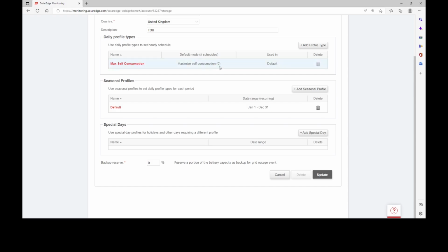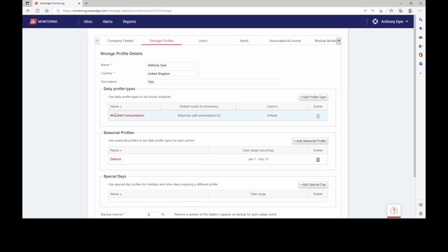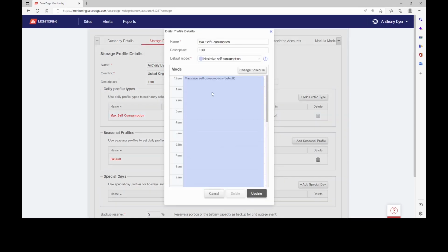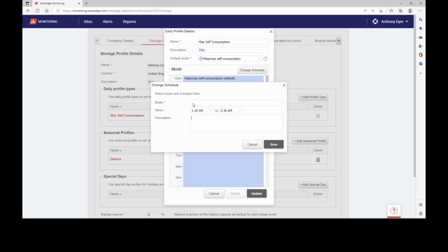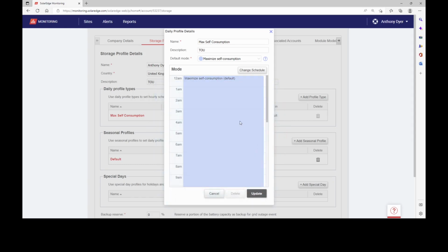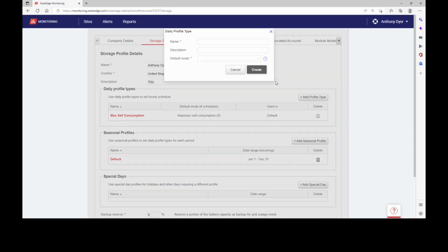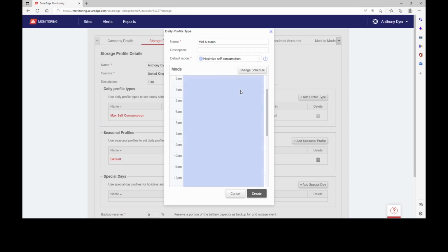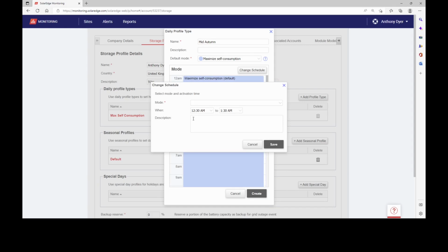So what we're going to do is explore the options here. We've got maximum self-consumption, and a mode that can be selected for each period of the day. We'll leave this on for 24 hours and create a brand new profile, which we'll call mid-autumn. The default mode will be maximum self-consumption, but in addition, from 12:30 till 4:30 we're going to set it to solar power only.